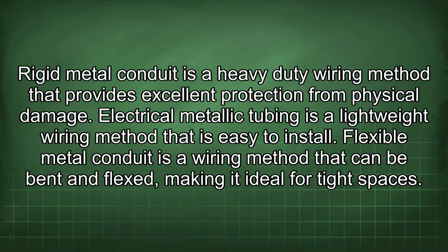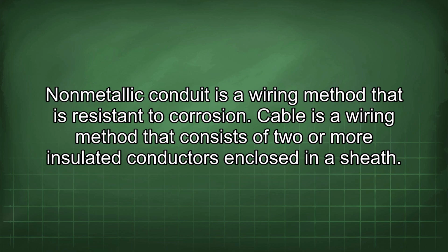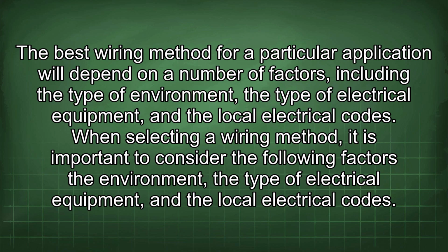Flexible metal conduit is a wiring method that can be bent and flexed, making it ideal for tight spaces. Non-metallic conduit is a wiring method that is resistant to corrosion. Cable is a wiring method that consists of two or more insulated conductors enclosed in a sheath. The best wiring method for a particular application will depend on a number of factors, including the type of environment, the type of electrical equipment, and the local electrical codes.